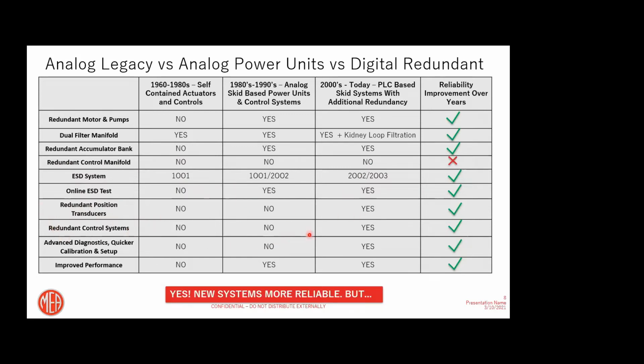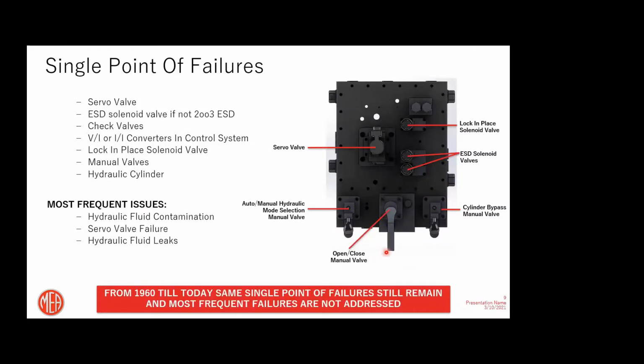Control systems, of course, an additional improvement. We went from analog boards to triple redundant PLCs, for sure. Advanced diagnostics, quicker calibration and setup, improved performance. Yes, definitely improved by a lot, as with PLC-based controllers we can now monitor, diagnose, troubleshoot and calibrate everything much more simply compared to the analog control boards.